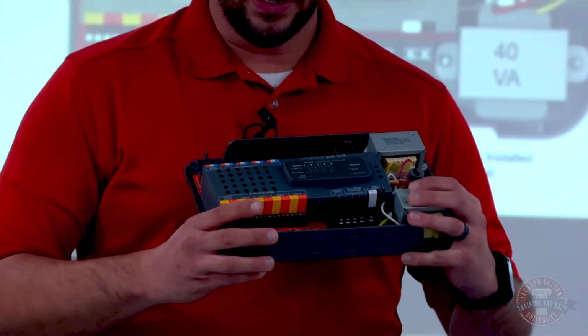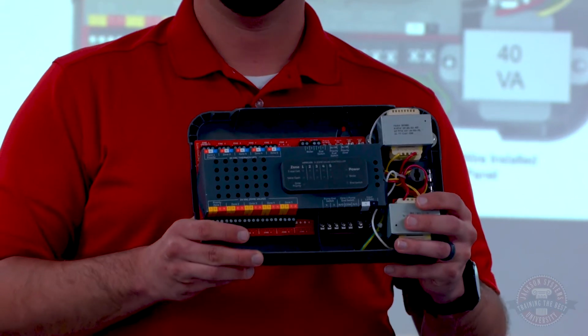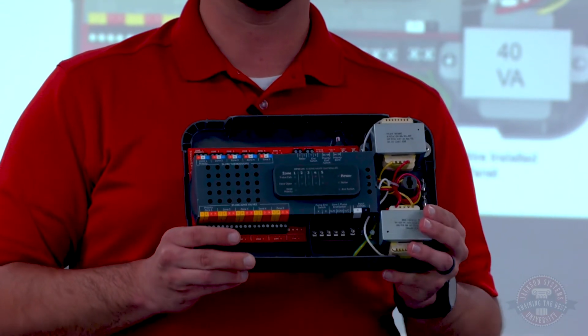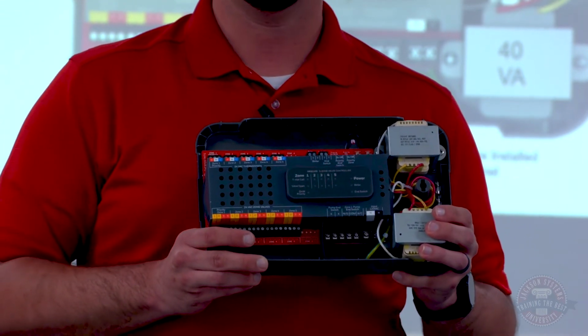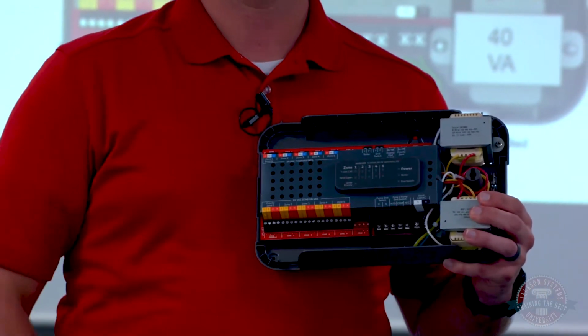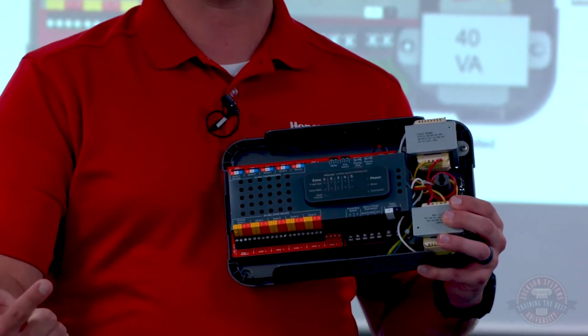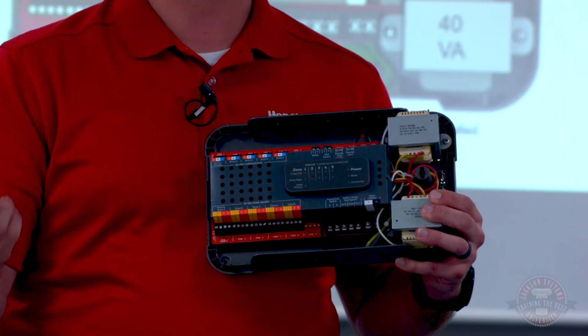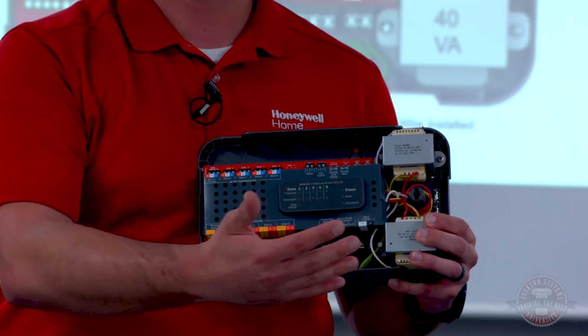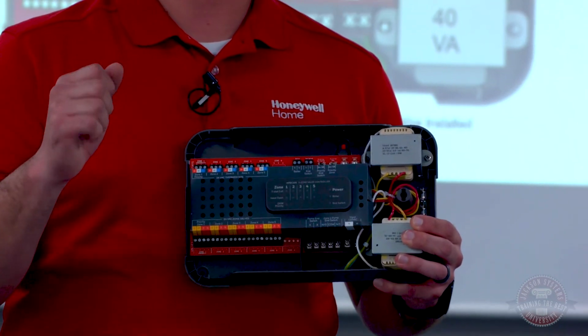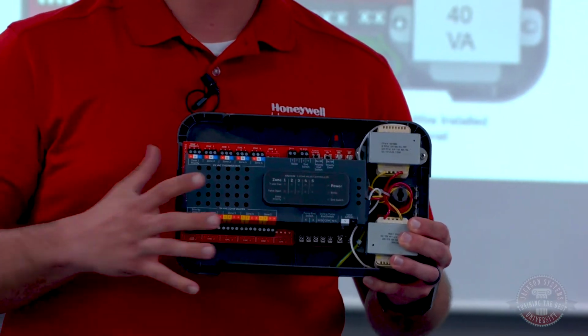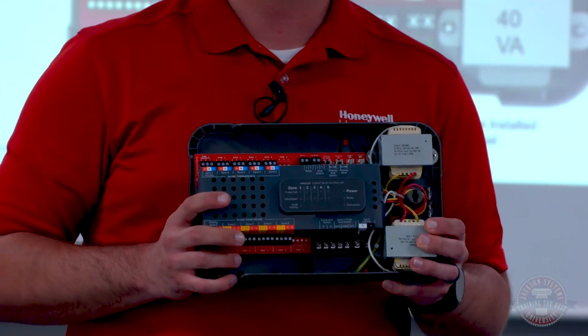So everything's color-coded, and it gives you a visual representation. You can walk up to a job site and immediately identify, at least by this, what zone is calling for heat, what zone valves should be open, what pump should be running, should the boiler be turning on, etc. So there's no getting out your voltmeter, there's no tracking stuff down. You can immediately figure out what's going on.